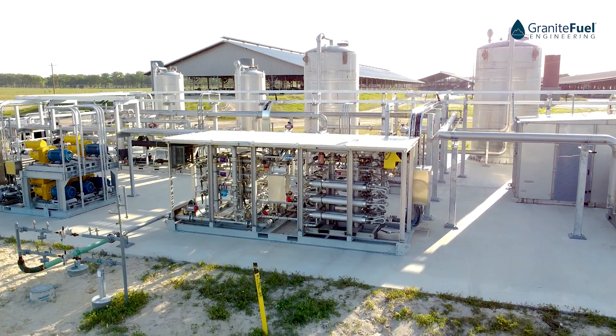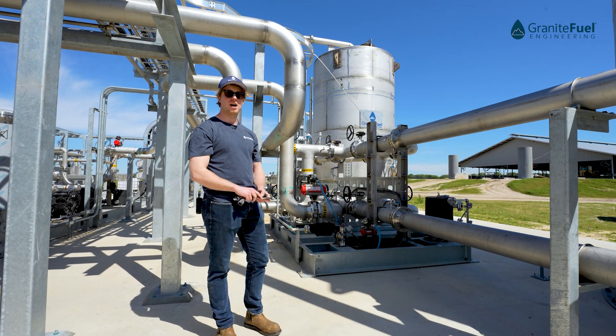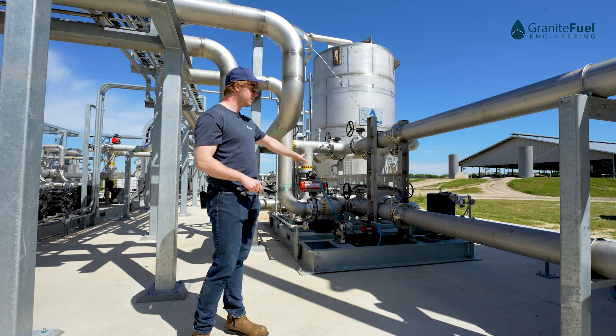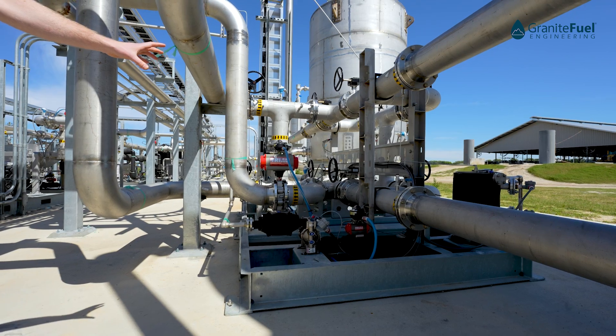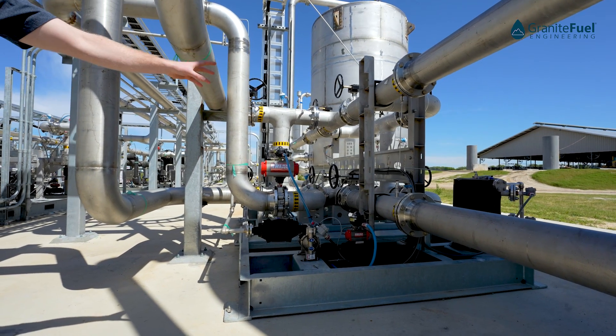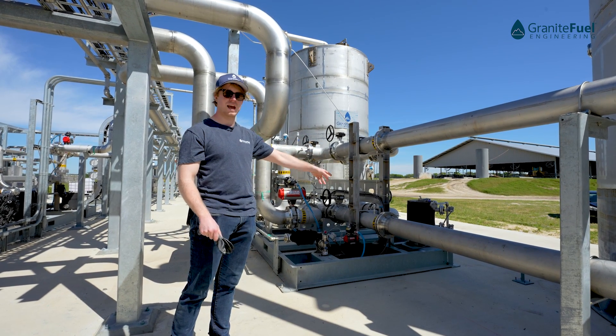The first step in our process is H2S removal. The system here includes two static media vessels, each filled with Ferrazorp media. In the center here we have our lead-lag valve skid, which is going to allow you some flexibility in how you operate the system. You can run your vessels in parallel or in a lead-lag sequence so that you can replace the media in one of the vessels while you still run gas through the other.